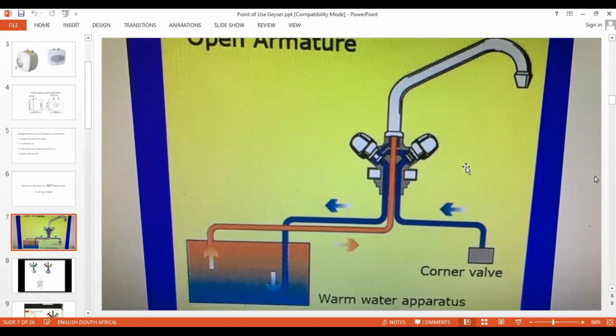So please explain to the homeowner and anyone else that's going to use that, if it's in an office or wherever, that when water heats up, it expands in volume. It'll push through the spout and drip. Once it has gone through the heating cycle and stops, the expansion will stop and the dripping will stop. That is normal function.